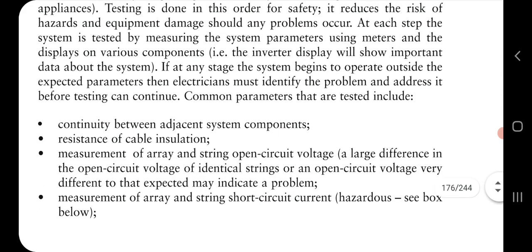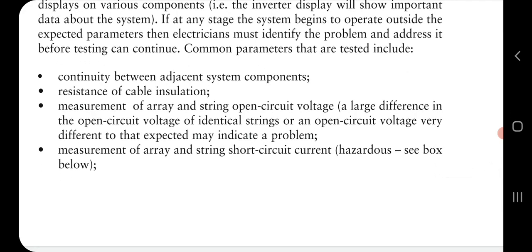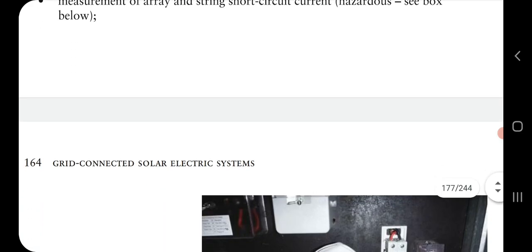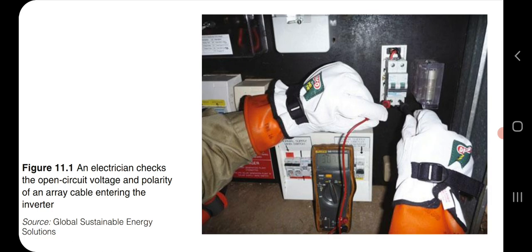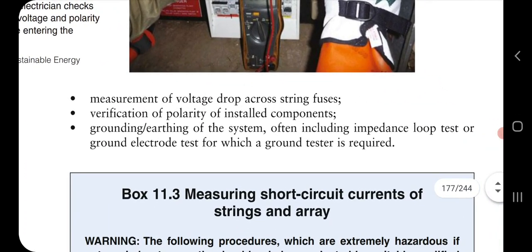The common things which have to be tested are the continuity test between two resistors or components, then the resistance of a cable. Insulation resistance is very important and has to be checked. Measurement of array and string open circuit voltage is also very important, and then short circuit current. You can see this electrician testing the equipment using a meter. Various parameters, open circuit voltage and short circuit current, have to be checked. Then voltage drop across the fuses, polarity, and grounding of the system also have to be checked properly.